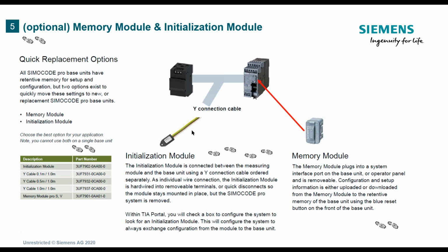With this initialization module, it's tied to that bucket space. It's sitting in the wireway, mechanically attached with a self-tapping screw. Notice the little eye hole at the top. As soon as he removes the bucket that had a problem and puts in the other spare bucket, all this is plugged in, and he cycles the power, it dumps the program into the Simocode, and they're up and running. So that's two ways of doing it.